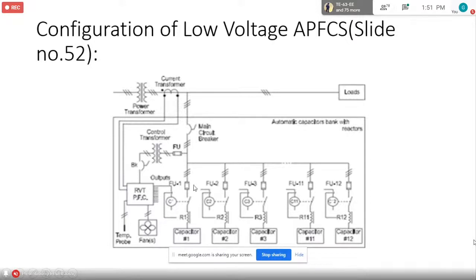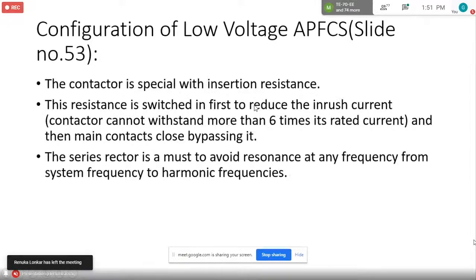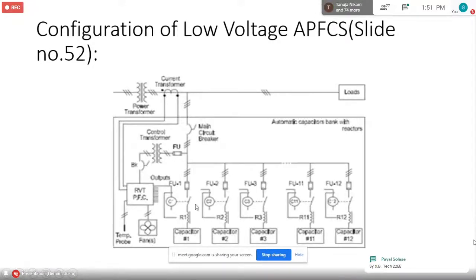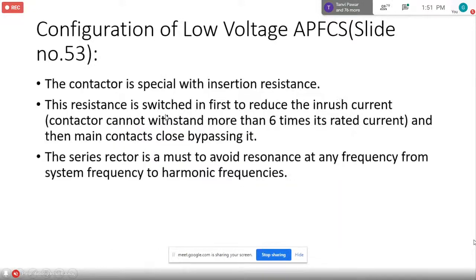You can have, instead of isolator and fuse, an MCCB also. The contactor is special, with insertion resistance. Remember, this contactor is capacitor duty. There are various categories of contactors, and this is the capacitor category. What it means is it has a resistance.